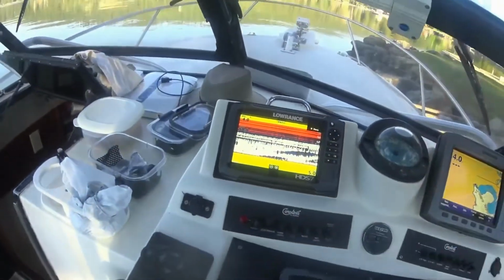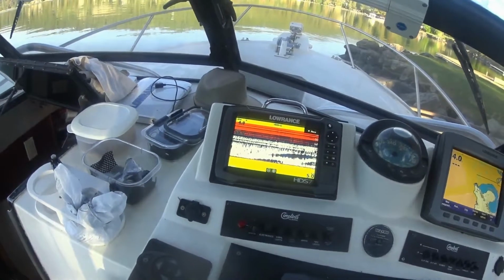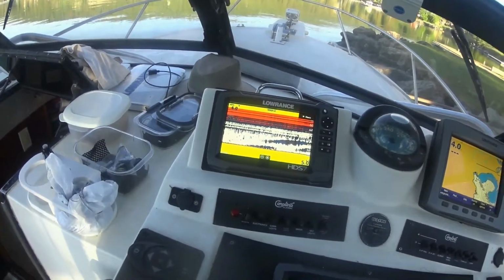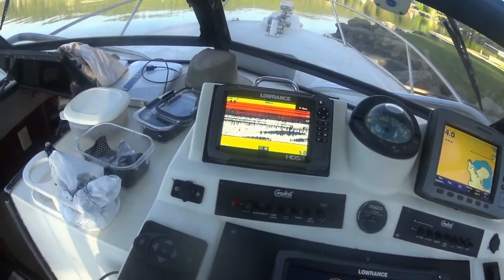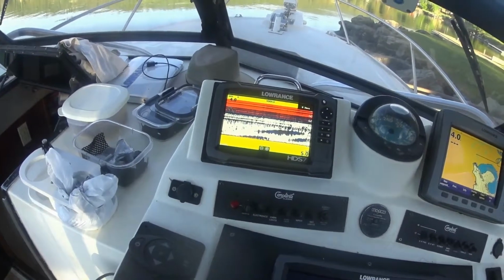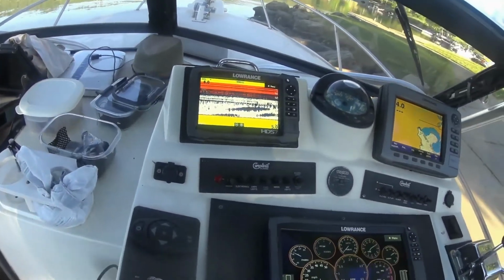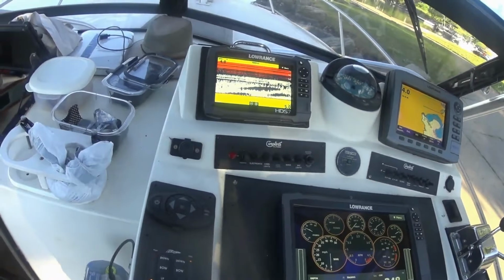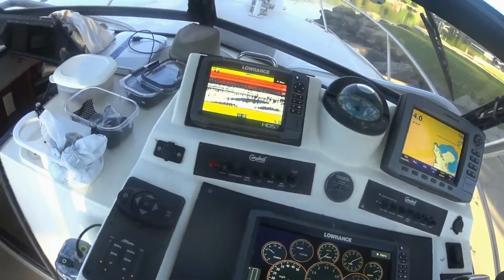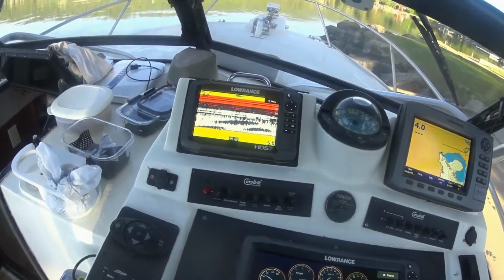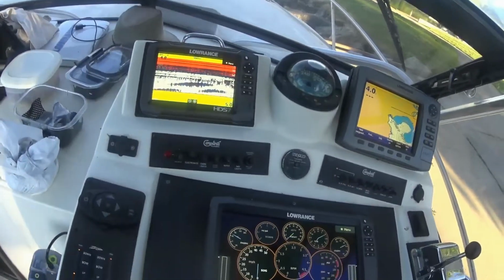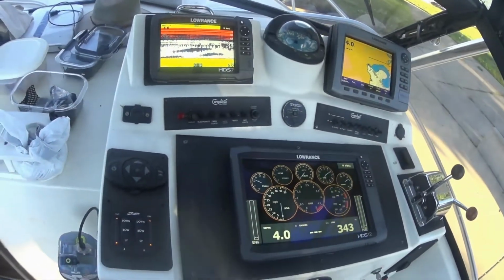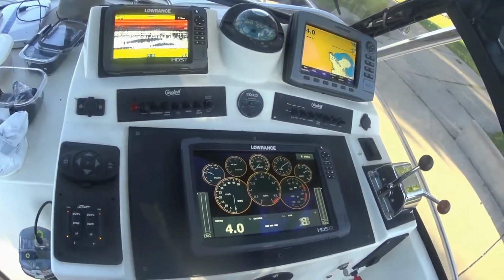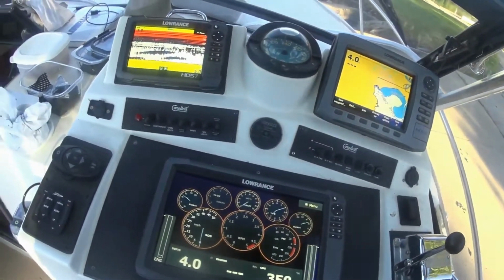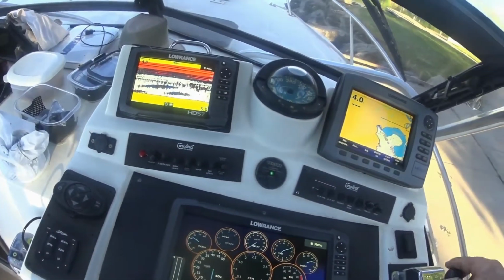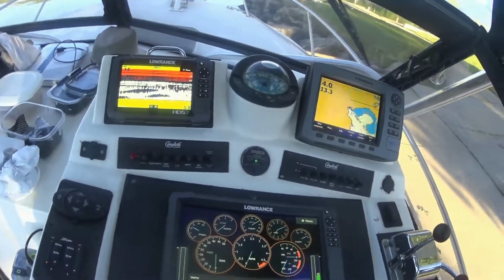We've held off a bit hoping the water temperature would come up from the low 40s to about 60. It's not quite there, but it's closer for a worst case cooling test. We don't want exceptionally cold water running through the raw water side, so we can get a good feeling for how well the heat exchanger is doing its thing. So no more talking, let's light her off and get things started.